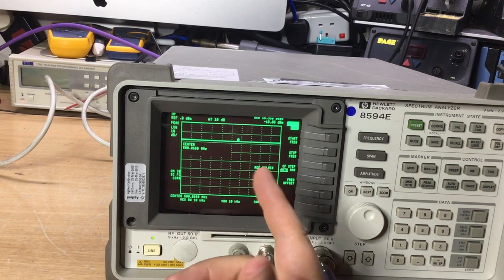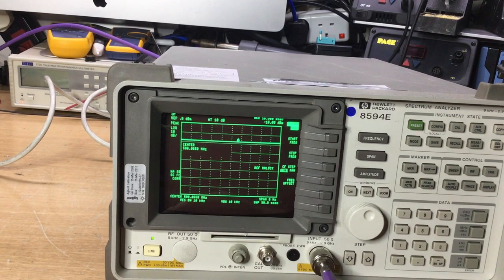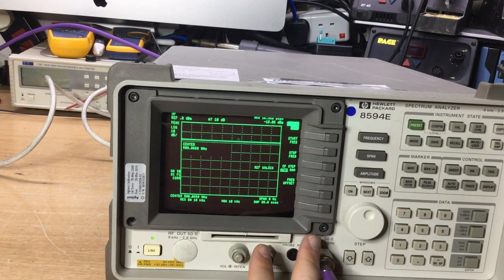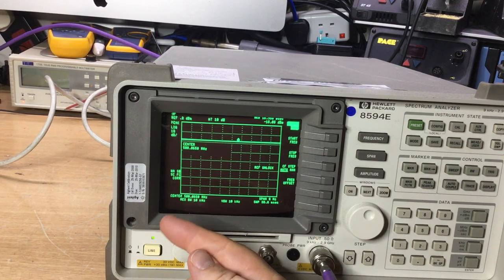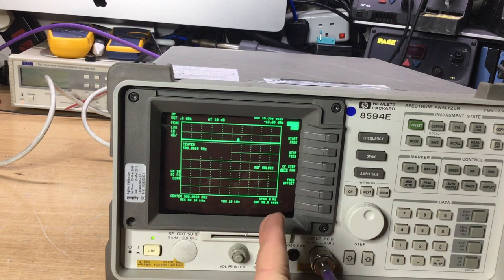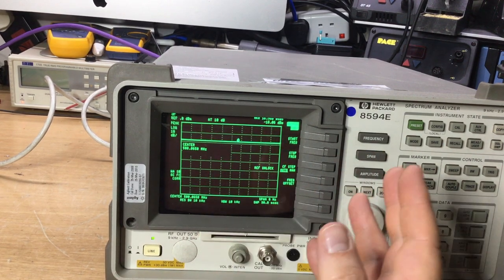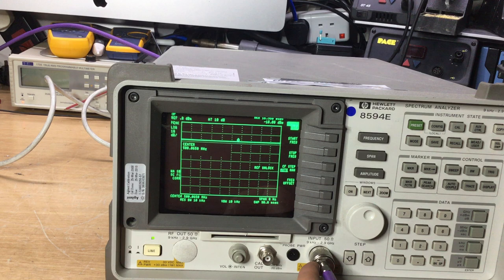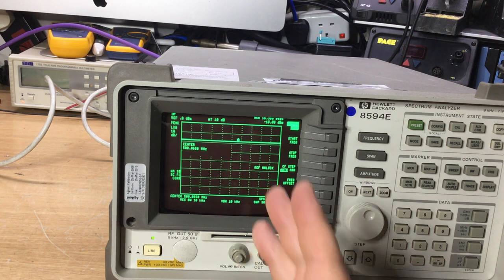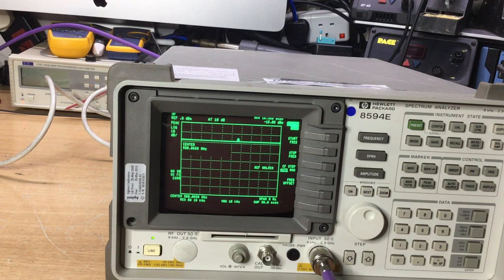So there's a couple of things really. The monitor's out of focus. Secondly, on the calibrate, it couldn't see either the frequency or the level, probably because the internal reference has wandered off, so we'll need to pull that back to spec. And then thirdly, there's the signal level discrepancy coming in, which is measuring 18 dB away from where it should be. So there's a few things to be going on with there.